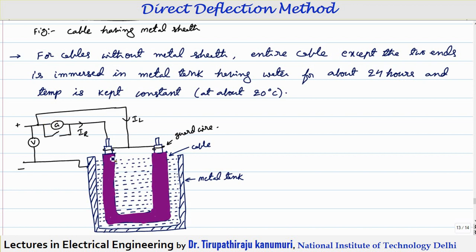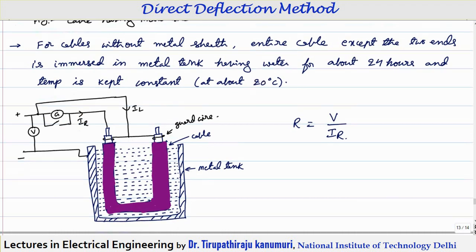So the leakage current will not be carried by your conductor. The galvanometer is connected to the conductor and it indicates the value of IR. The insulation resistance is equal to voltage measured divided by IR. Whatever current is leaking from the conductor through the insulator through the saline water to the negative terminal is not measured by the galvanometer — that is the reason for providing the guard wire.